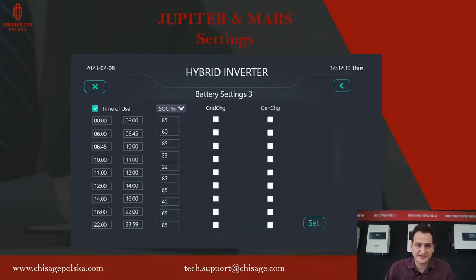The third page of battery settings is the time of use settings. As I said, we can set 9 time ranges, and the state of charge or the battery voltage for all these times. We pick which time, what state of charge, and then we set whether we want grid charge during these hours or not, and whether we want gen charge during these hours or not. This page is more important for the inverter than the previous one. If time of use is picked, the inverter will work with this page, not with page number 2. So it doesn't matter what we put in page number 2 if we use time of use mode.